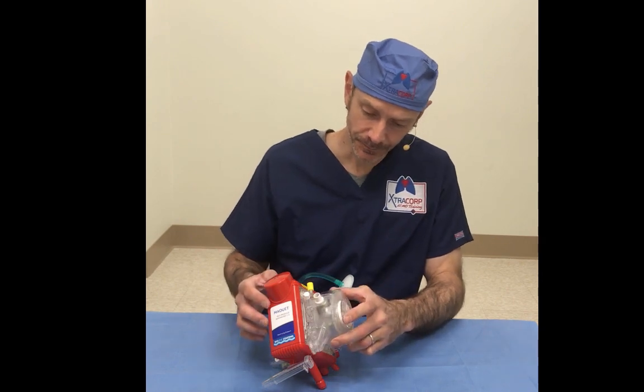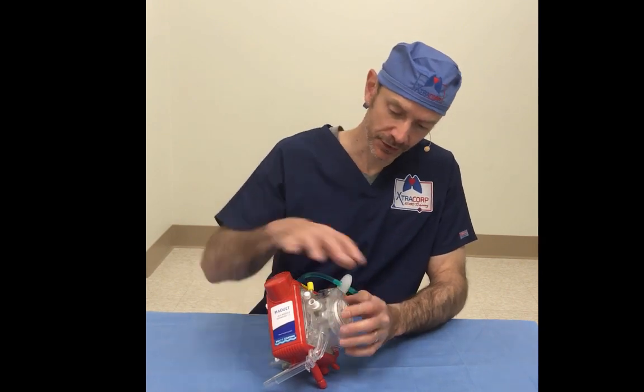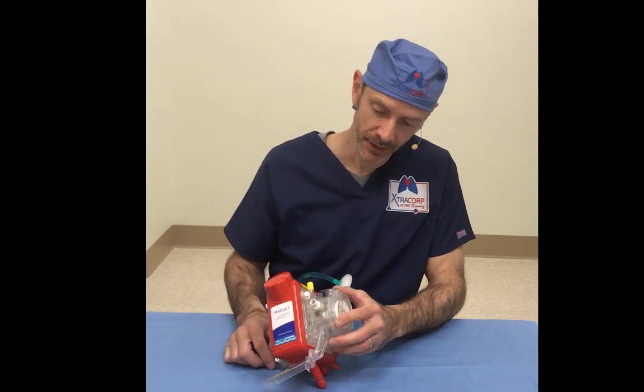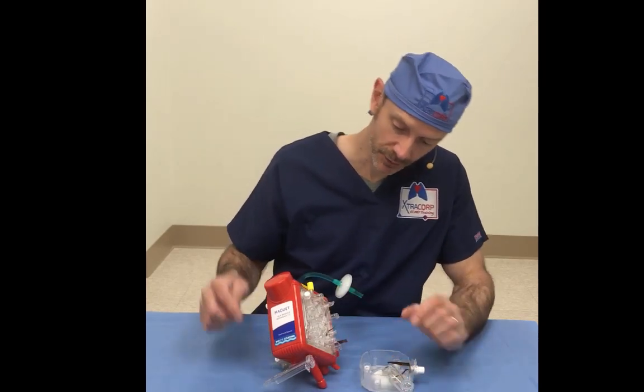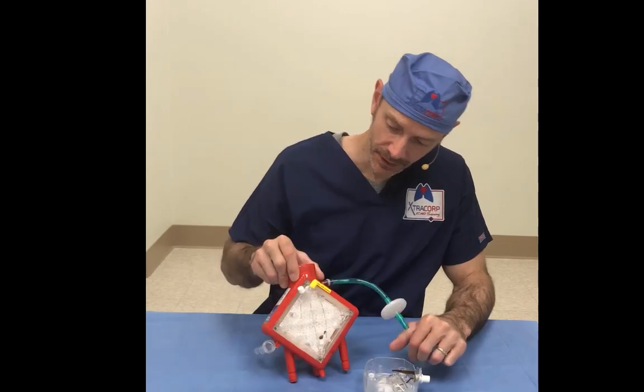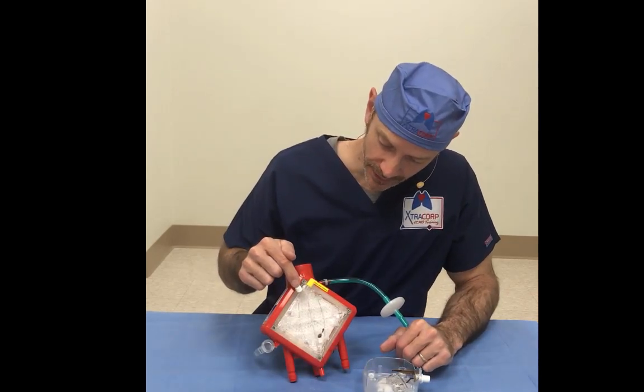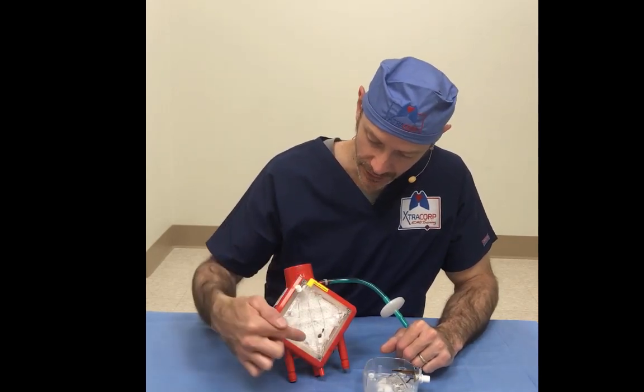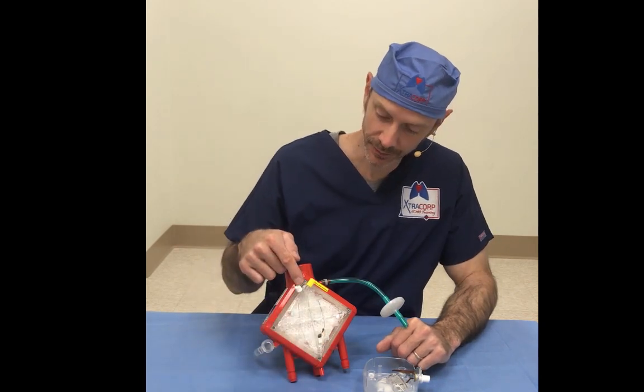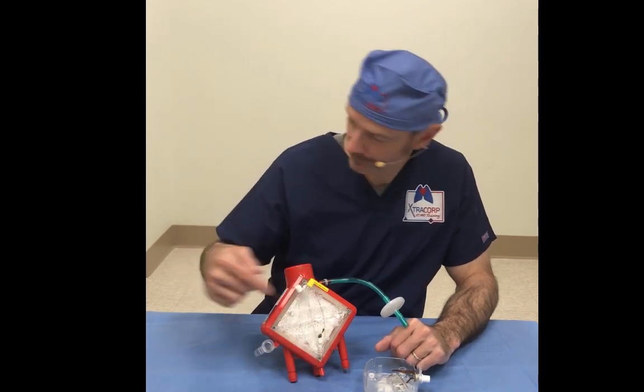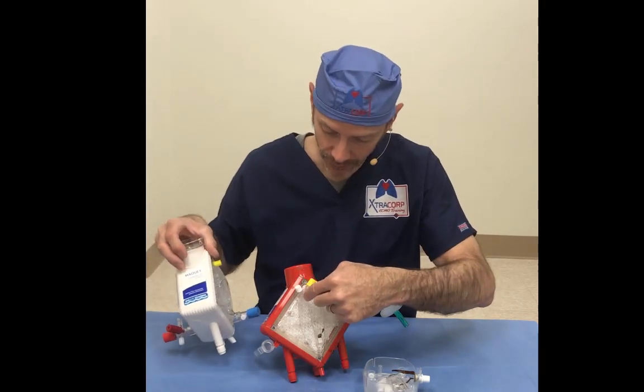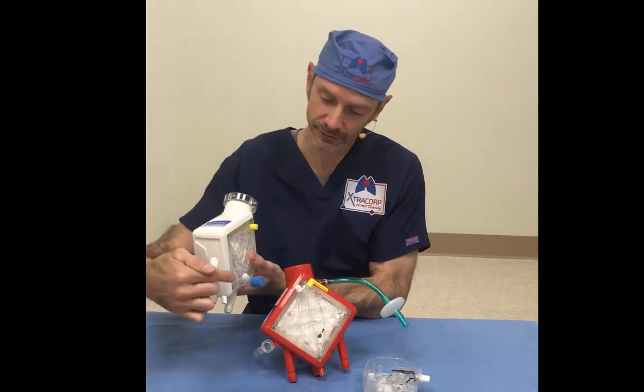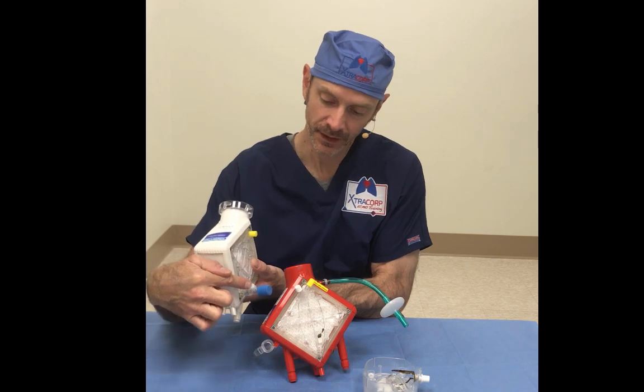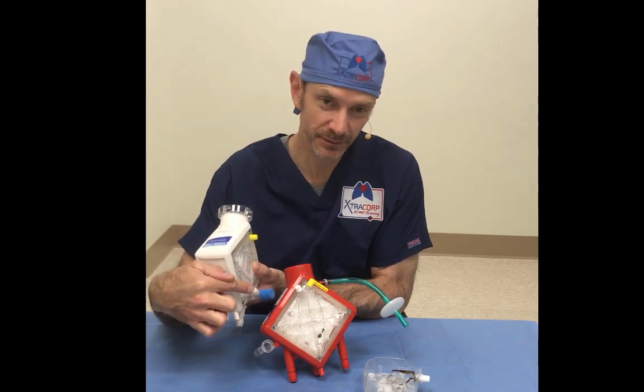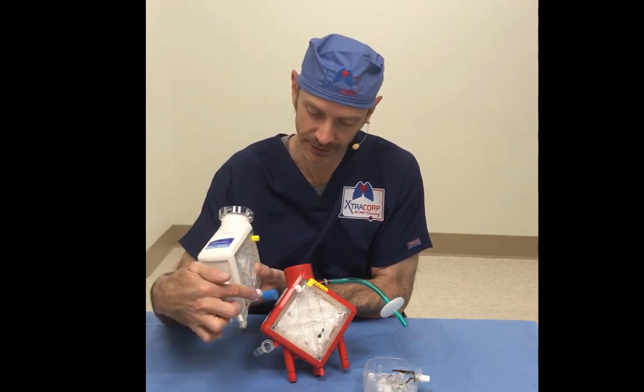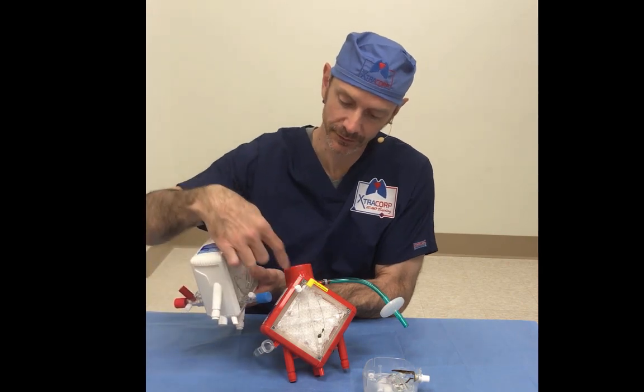Now because this covers so much of this face of the oxygenator, then they had to move something, and they moved the pre-membrane port. That pre-membrane sample port is not on one of the channels, but it's right up here near the top, and it actually interfaces right there. So that port right there is the equivalent of this port right here, equivalent in function, but there are some very minor technical differences with having it at the top versus the bottom.